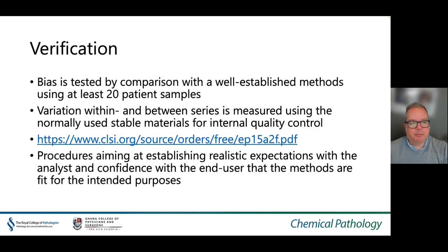In a verification experiment, bias is one of the most important experiments and can be tested by comparison with well-established methods using at least 20 patient samples. The other most important assessment is of imprecision, and variation within and between series is measured using stable materials or internal quality control. These procedures are aimed at establishing realistic expectations with the analyst and confidence with the end user that the methods are fit for the intended purpose.